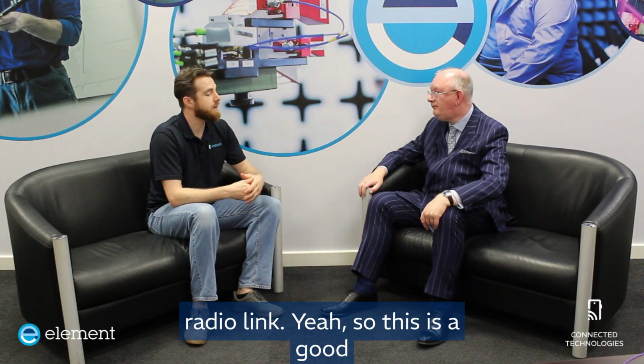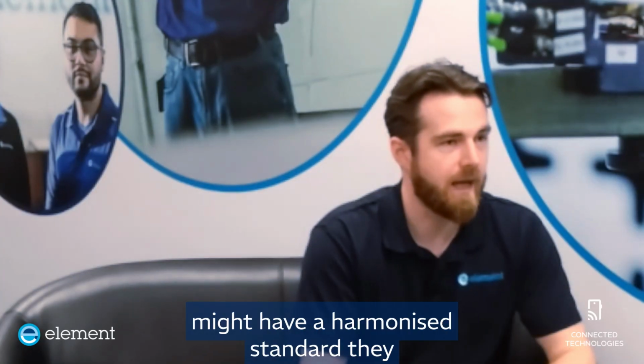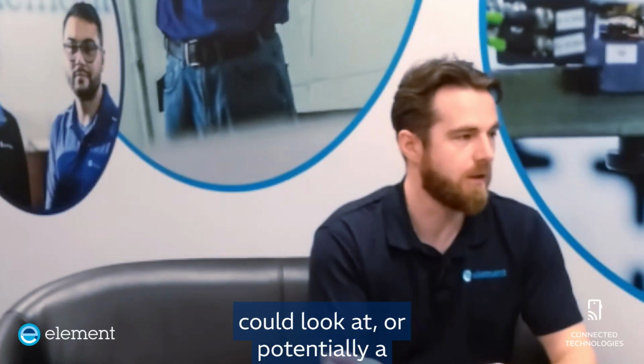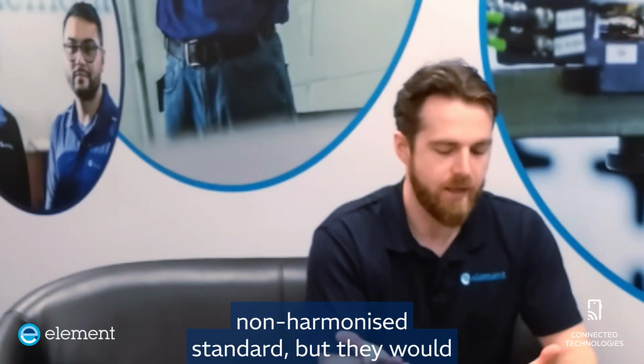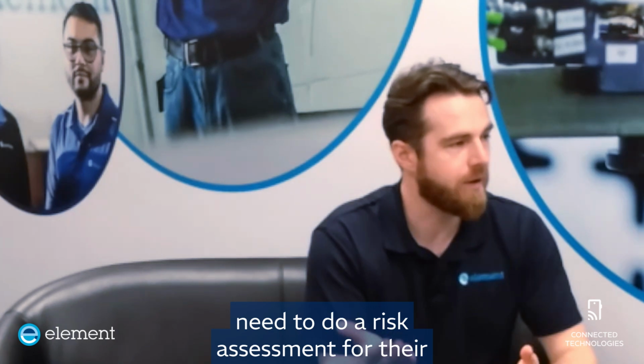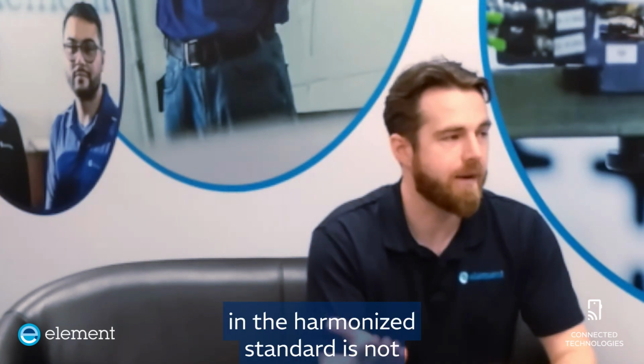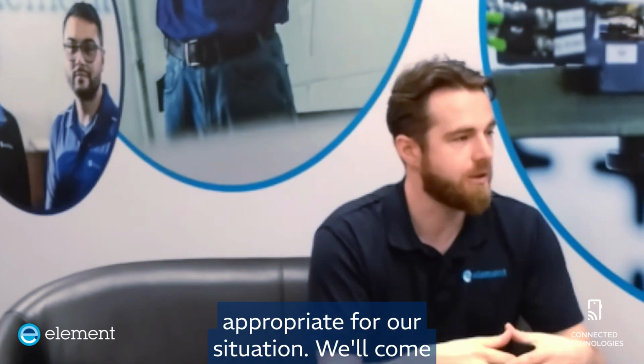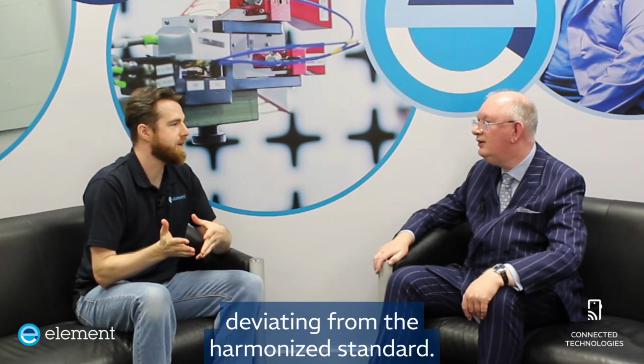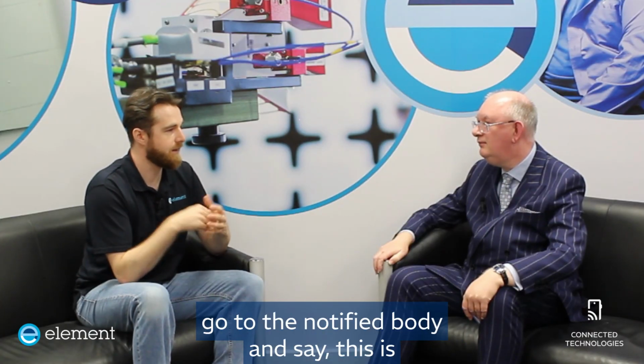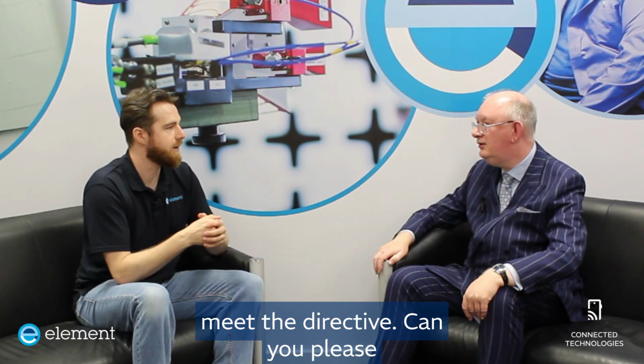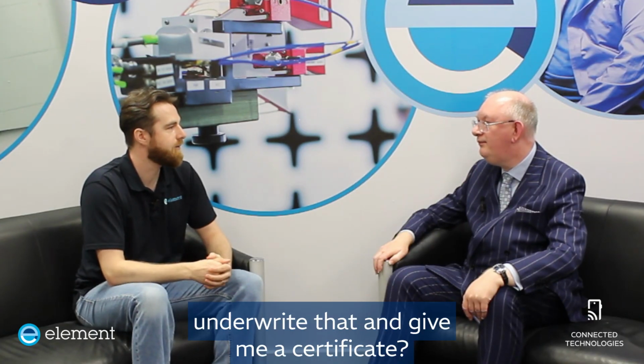So this is a good example of where a manufacturer might have a harmonised standard they could look at, or potentially a non-harmonised standard, but they would need to do a risk assessment for their product and say, actually, the test in the harmonised standard is not appropriate for our situation. So we'll come up with our own test, our own set of performance criteria, possibly deviating from the harmonised standard. And if it was for an Article 3.2 radio spectrum issue, they'd then have to go to the notified body and say, this is what we've done, this is why we think we meet the directive. Can you please underwrite that and give me a certificate?